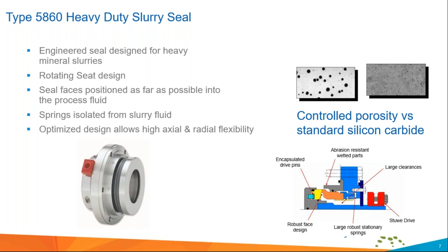All mechanical seal technology relies on a very thin film of lubricant between a rotating and stationary set of very flat wear faces. Whether this lubrication is provided by the fluid being pumped or by an introduced liquid, the consumption of this media is extremely low. Correct design choices and proper engineering can minimize or eliminate the need for external water flush. Mining slurry is a technically challenging application for mechanical seals — that's the understatement of the day. The key factors we need to address are solids percentages, particle hardness, and particle size.